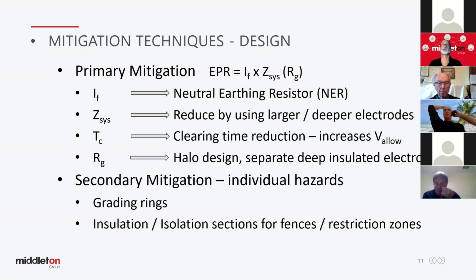So let's bring Ohm into this, Ohm's law. V equals IR, or in earthing terms, we like to talk about EPR equals fault current times the system impedance. So if we want to reduce the voltage, quite obviously we either reduce the current or reduce the impedance. Or in the case of just a separated grid on its own, we call it RG, the resistance of the grid. One classic way to reduce the current is to introduce a neutral earthing resistor in the supply feeder. If you can bring your fault current from 10k down to 1k, you've automatically reduced your EPR and touch voltages by 90%. We can reduce the grid resistance or system impedance by using a larger grid or deeper electrodes. So basically putting more copper in the ground to reduce the resistance path through to the earth, which is the return of the fault current back to the supply point.